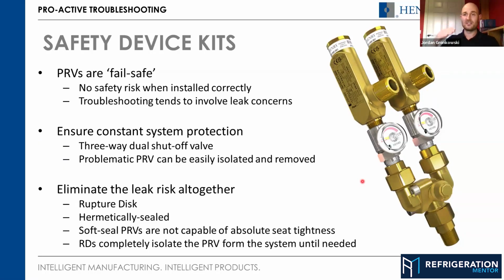If you think about a PRV where you've got a Teflon seat and a Teflon seal like a brass or a steel seat, all you're doing is pushing these two surfaces together. Like, that's never going to be hermetically, it's not possible for this to be hermetically sealed. So you'll always get, in every PRV, a small weep, we call it, of refrigerant through, and it's not enough to set off a leak detector. You wouldn't notice it with any detection equipment.